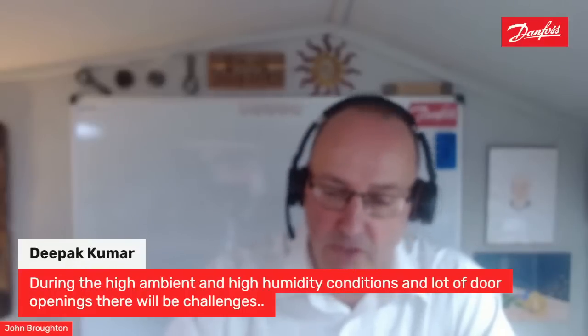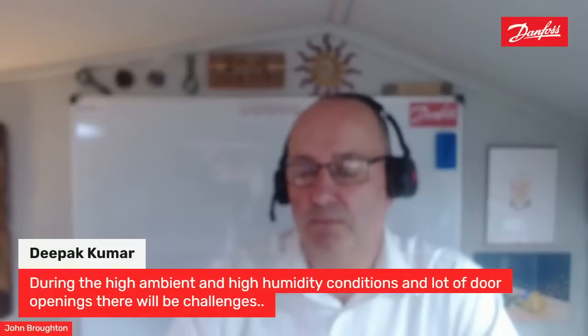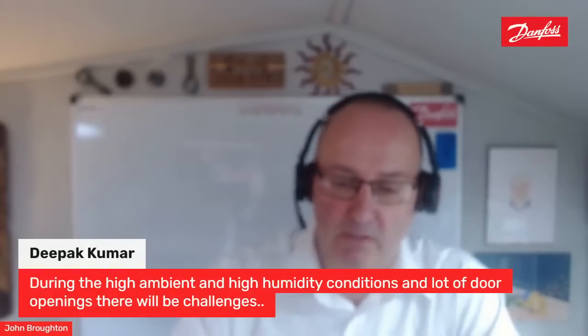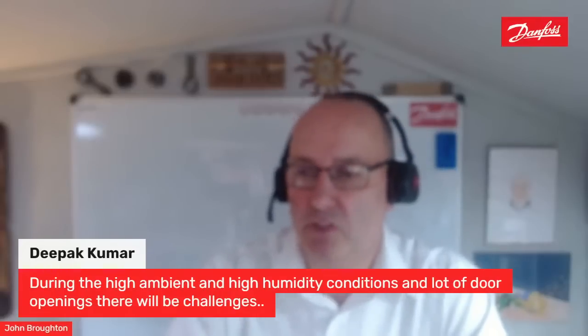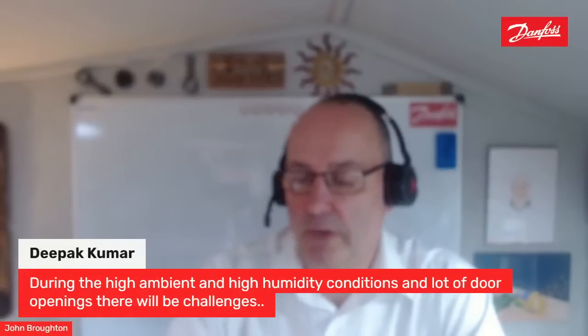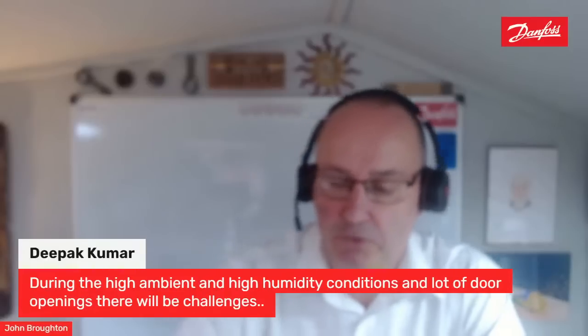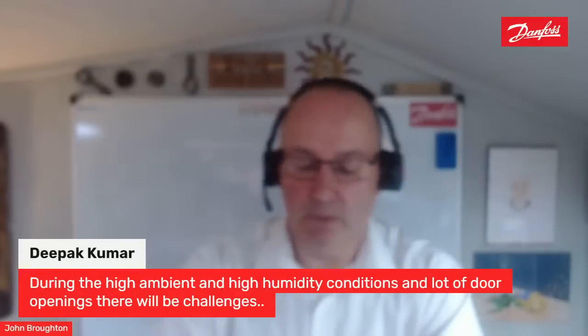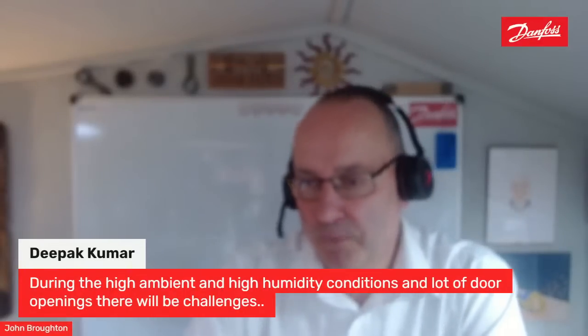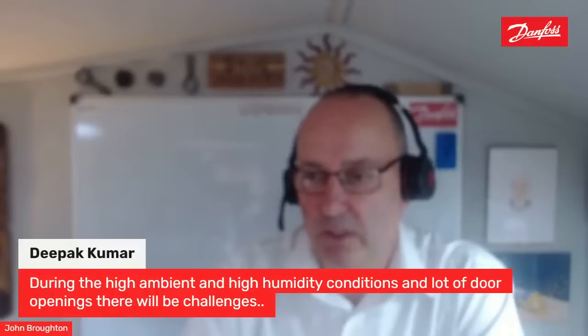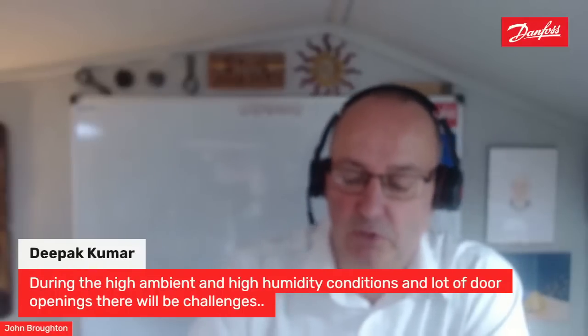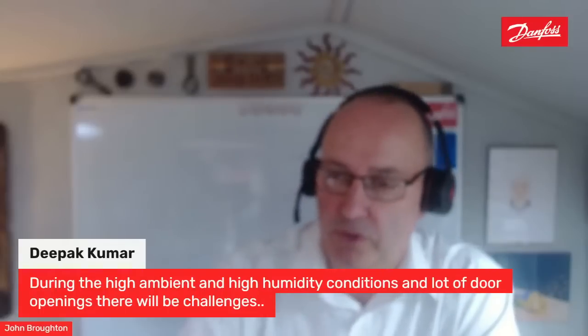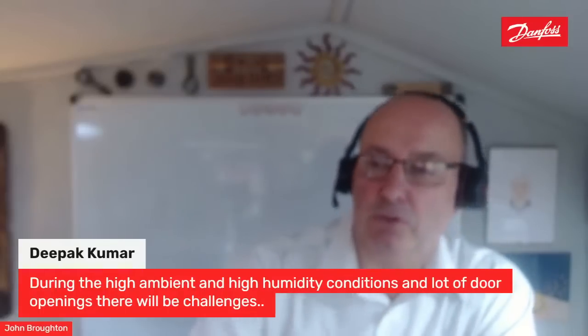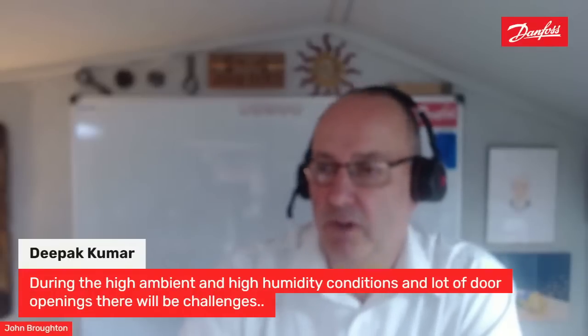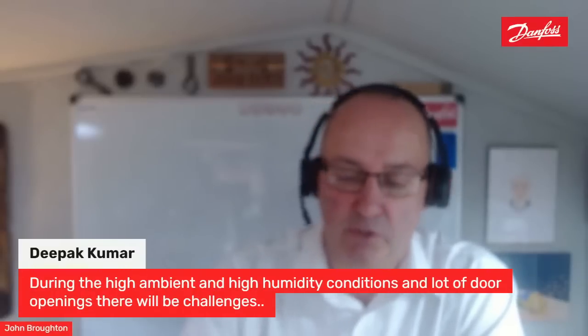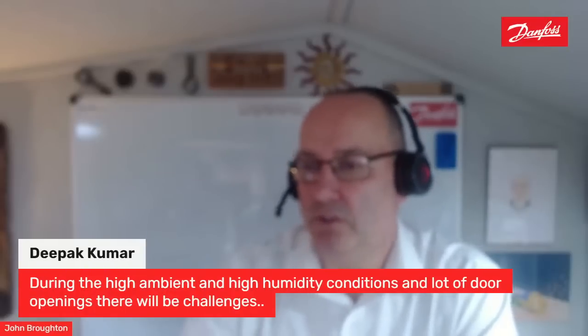There's a few things you can do. If it is just a walk-in box, we have those challenges, and we just have to maintain a very good defrost scenario, making sure that every defrost actually cleans the frost off the cooler. Again, we've got to keep an eye on the temperature. You can also link it so that when the door is open, the refrigeration system is off, so we don't absorb all that moisture on the back of the coil. Again, not very good if that door is open 7 hours a day. You need that refrigeration system to work.